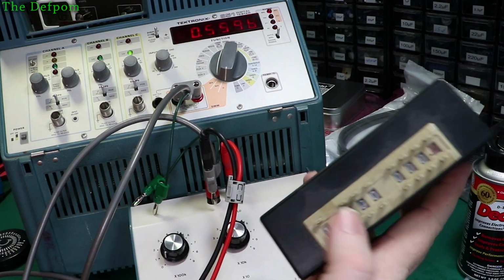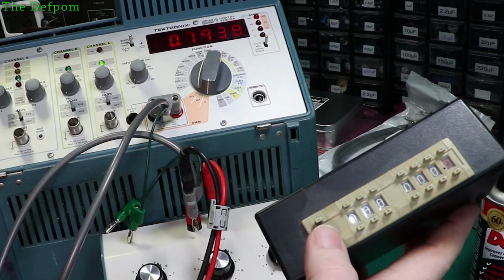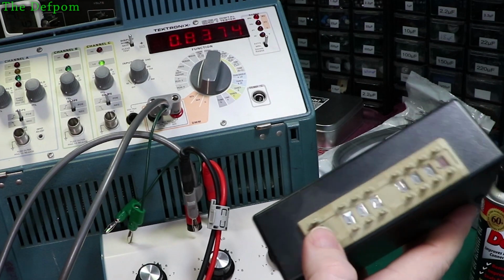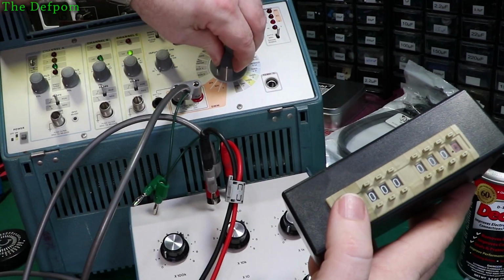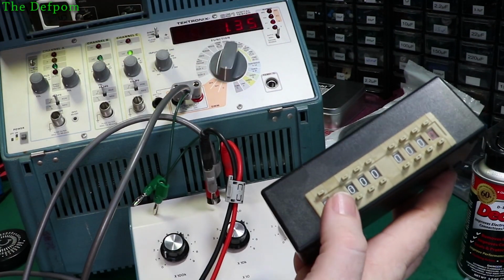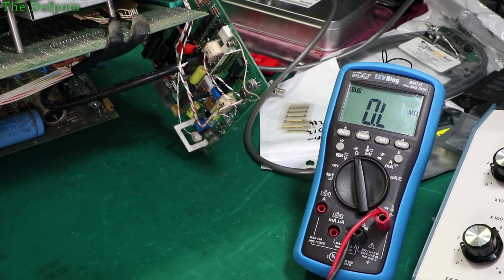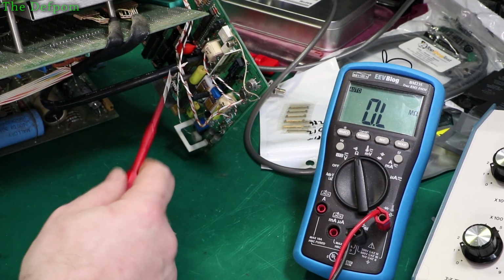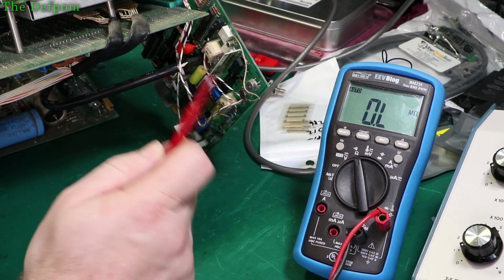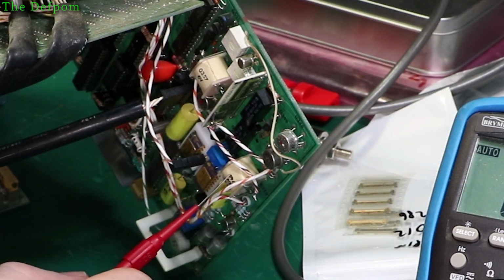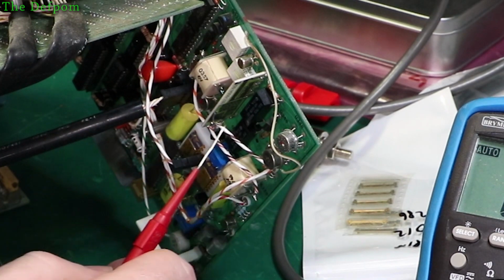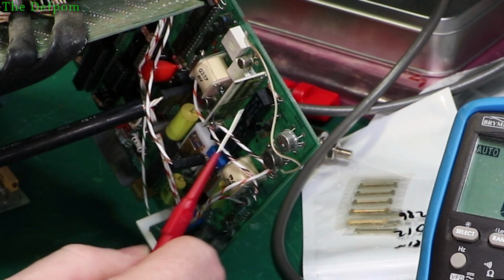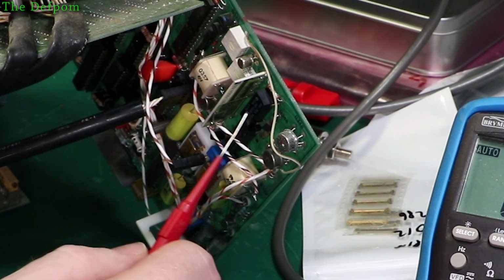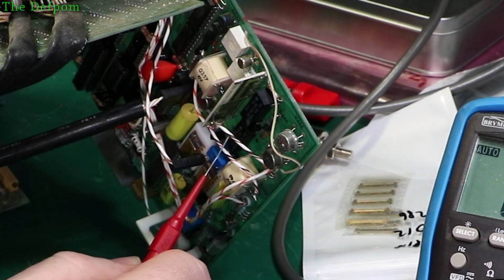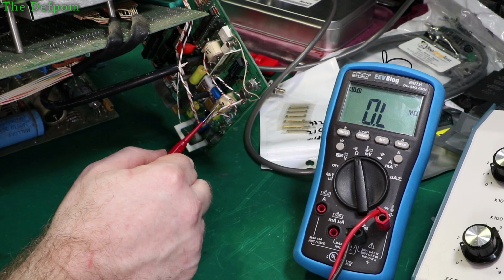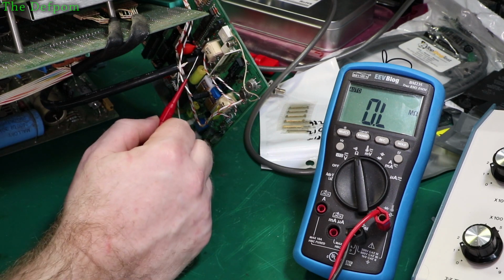I don't completely trust this box though. The megohm range is playing up. See that? So that's the one I swapped out. So maybe there are 2 relays that are bad. Maybe the one I put in is also not good. So I'm going to test these relays. Now there's 4 relays here, which I'm going to test. I've got these 2 larger ones here in the cream packages, and they've got these DIP ones. These ones here I've already swapped over thinking these were the fault, and they weren't. I swapped those and it didn't change it. So I think the problem is going to be one of these other ones instead.